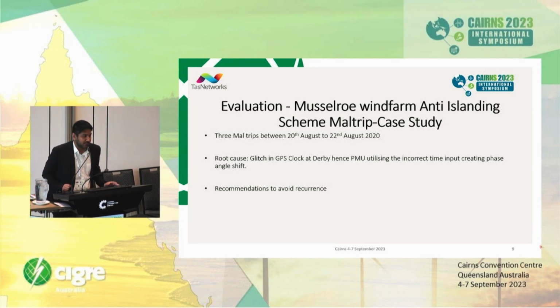Now, the question: we were thinking that if the data is corrupted, it shouldn't have been picked up by the PMU. It should have been declared as error data. As we know, we use a parity bit for IEEE time error detection. But when we talked to the manufacturers, they told us that if the parity bit remains the same, so if it's an even parity in the sender frame and again an even parity in the receiver frame, we won't be able to detect it.